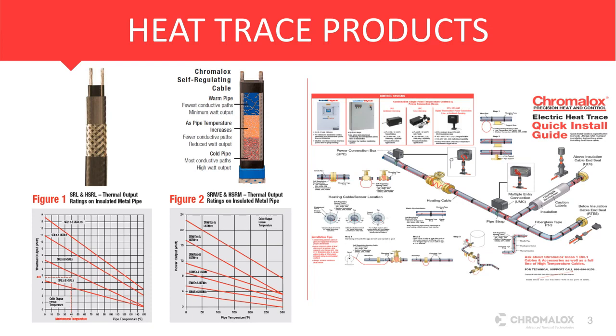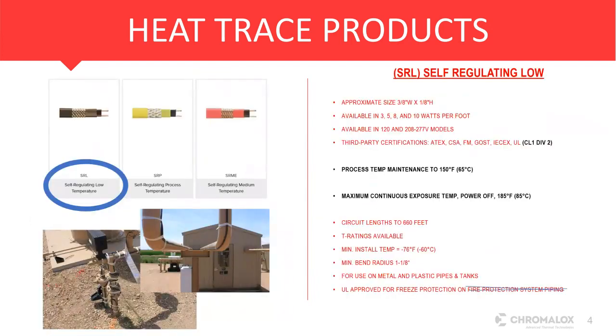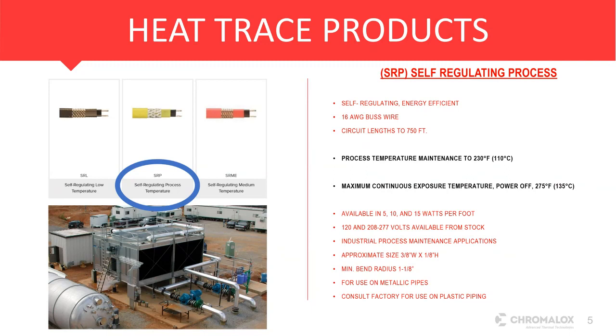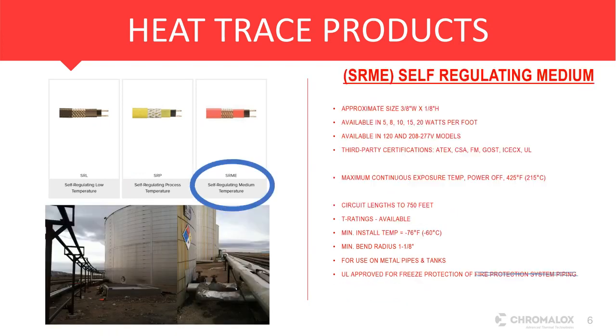So to start with, as you know, all heat trace manufacturers, we have what we call our SRL line. Next slide. Our SRL line, this is your typical freeze protection, standard low temperature stuff. From there, we have what we call our SRP line. P is for process. This is for your higher temperature process lines, maintenance lines, maybe chemical facilities, up to about 230 degrees F. If anything goes beyond that, we have our SRME line of products. That's good up to 425 temperature. So you think of your oil and gas applications, your chemical plants, and these are all products that are stocked on our shelves that we'll show you here in a second.